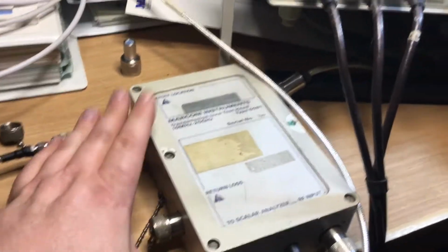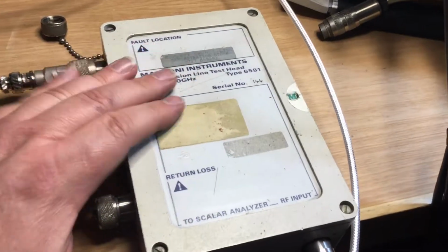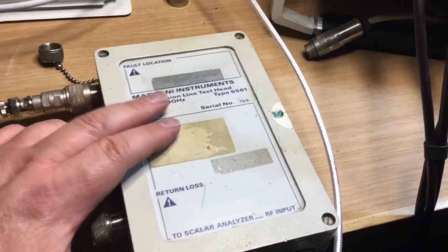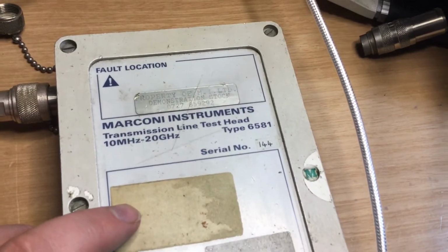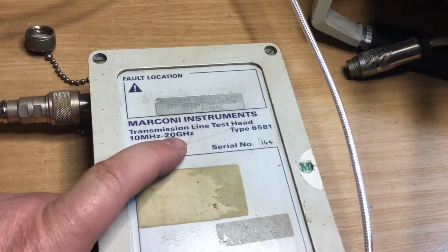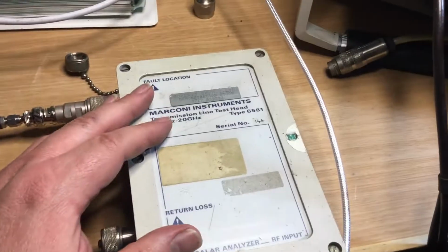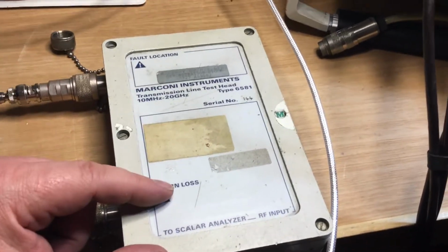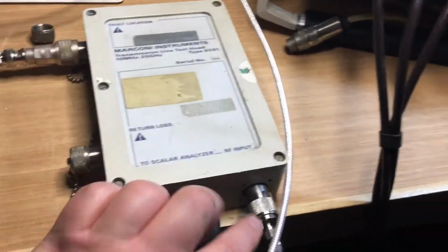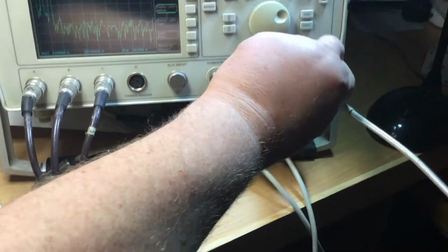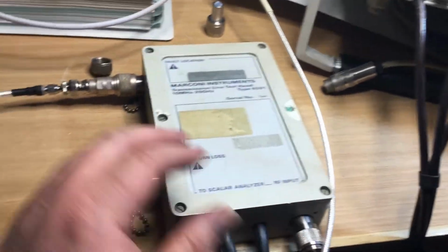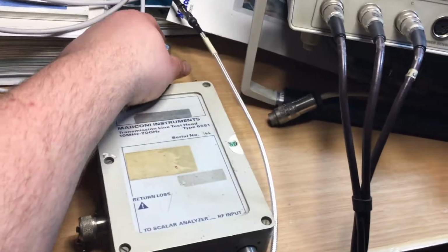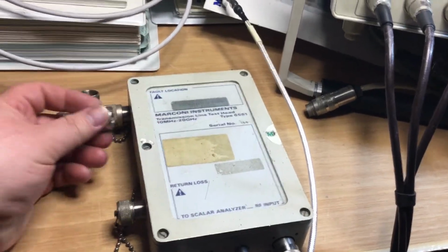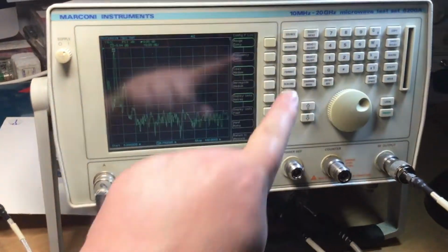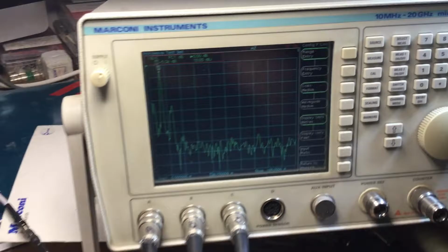Okay, we've now connected the fault head up, the directional fault location head, which is this 6581, 10 MHz to 20 GHz frequency range on it. This does quite a bit actually, not just fault location, it also does return loss as well. And we have a socket here which connects up to the radio test set's microwave test set output, so that's where it gets its signal feed from. We calibrate this as well with just a load for fault location, where we go through a calibration sequence on the test set under cal for this particular fault location mode.